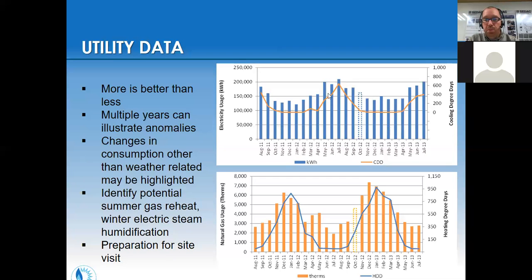We've put this cooling degree day line down here a little bit to illustrate that we think that we know that this library had a lot of electric humidification. So we're trying to illustrate that this is not typically what we would see in a building, and this electric humidification is using electricity in the winter beyond what we would normally see. And then air conditioning wise, it's using more in the summer than we'd expect as well.